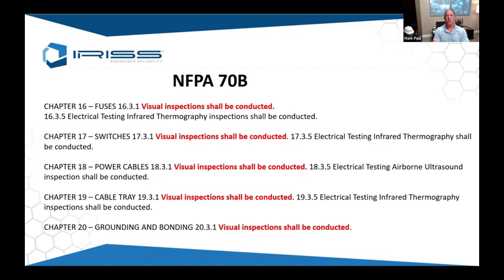So when you do the visual inspection, you can actually see that something was either completely good or there's an issue somewhere. NFPA 70B is going to be enforced, in my opinion, more and more rapidly by insurance providers, because they're looking for their way out of not having to pay. If they're insuring a large company that isn't complying with the standards set, that's their way out, and if they can get out, they will. If they're insuring somebody and there's an incident, they need to make sure we've done what we were asked to do. That's why we're seeing such strong demand for this in the marketplace.